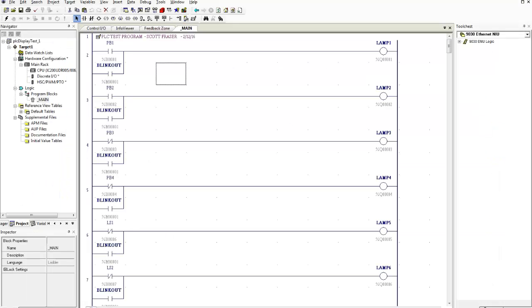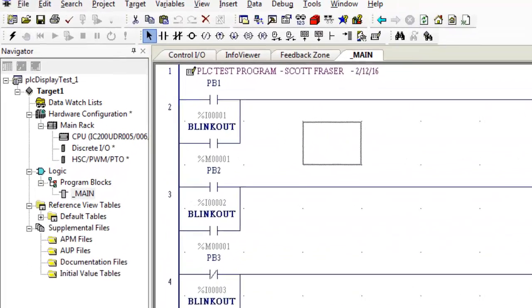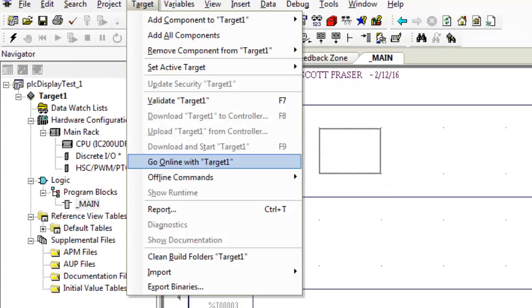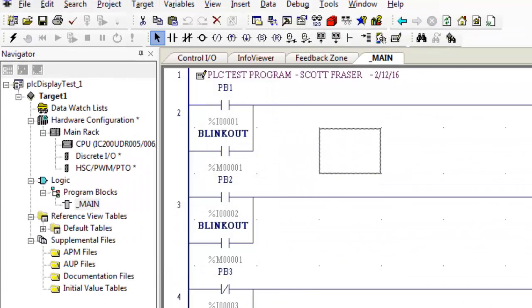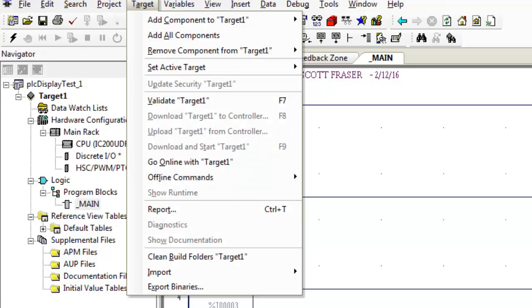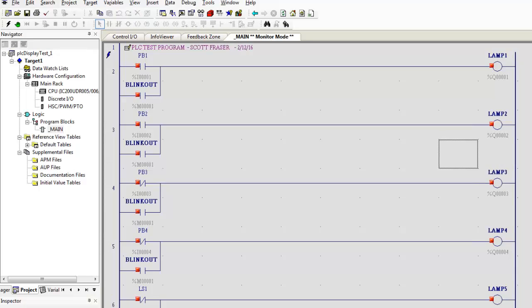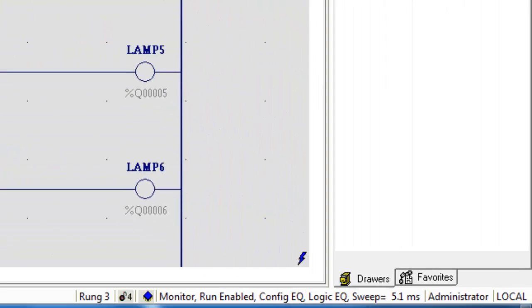The next thing we need to do is download it and install it into the computer. So you'll want to go up to target. Go online with target one. It goes through its things. You can see it going through and connecting the status thing. Status bar will show up and if you look down here you'll see some information. You'll see some sweep time. You'll see some logic and everything information. I've downloaded this program into it so it's telling me my configuration is equal and my logic is equal.